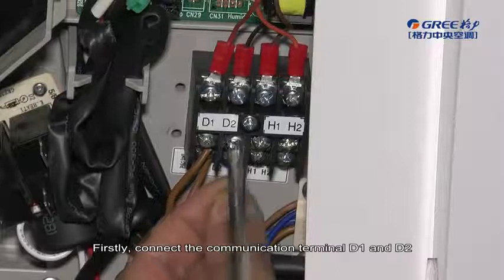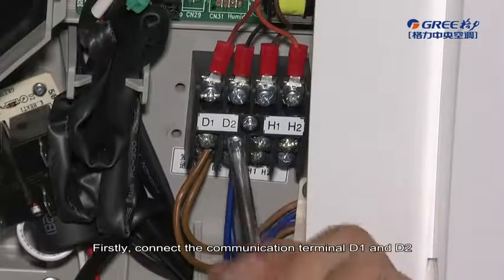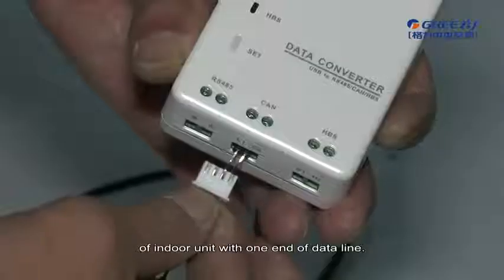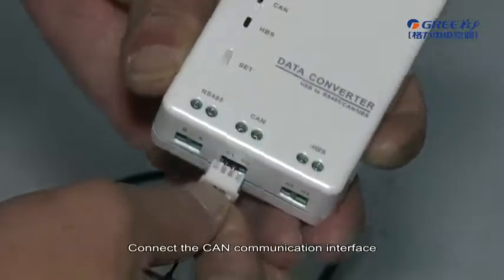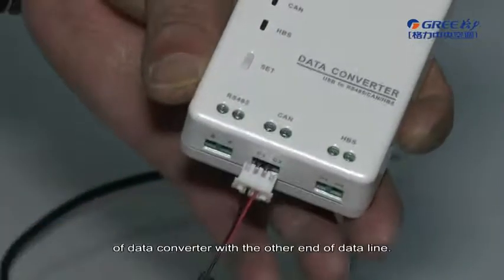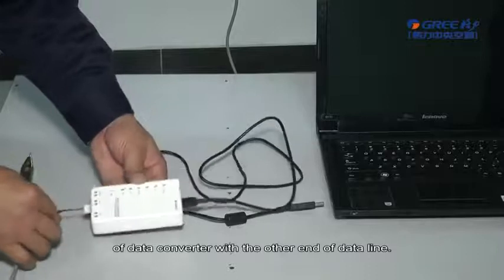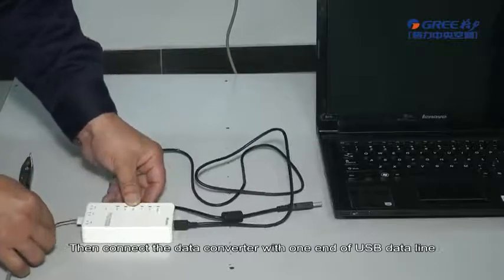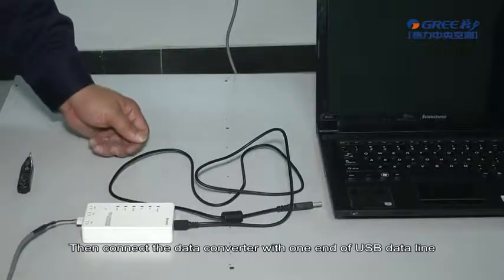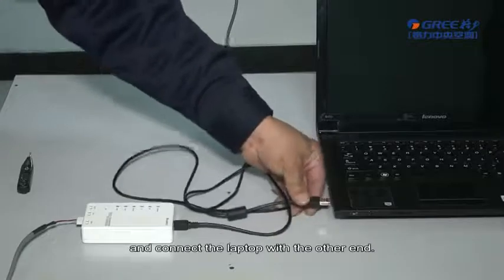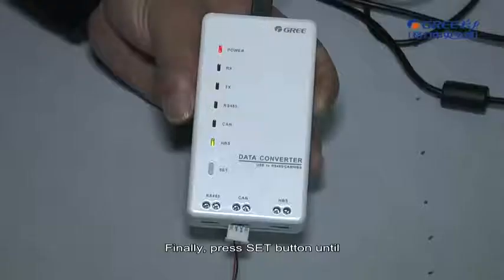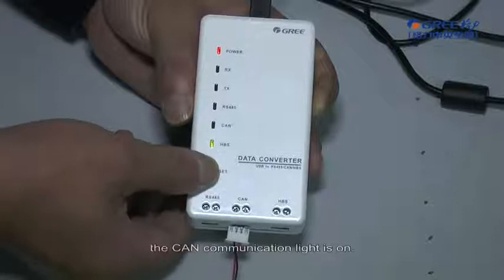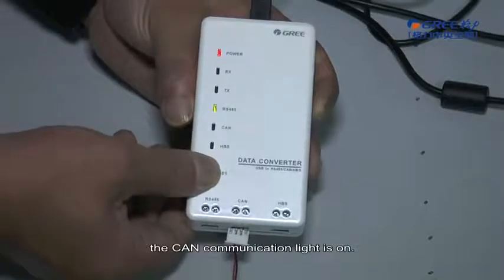Connection way. Firstly, connect the communication terminal D1 and D2 of indoor unit with one end of data line. Connect the CAN communication interface of data converter with the other end of data line. Then connect the data converter with one end of USB data line and connect the laptop with the other end. Finally, press Set button until the CAN communication light is on.